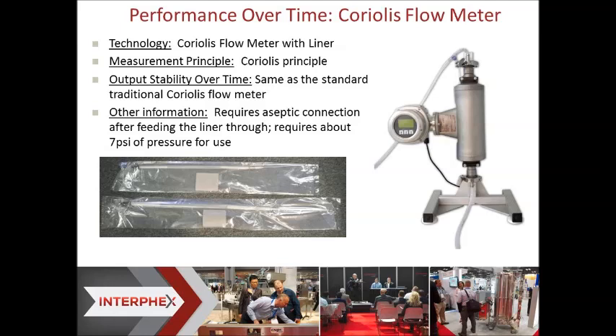As far as the Coriolis flow liner, this technology allows you to use a traditional Coriolis flow meter and eliminate the need for any cleaning or cleaning validation and potential sterilization. It does require an aseptic connection because it needs to be fed through the liner, and it requires about 7 psi of pressure for use. So there's a lot of people that want to use this technology, but they maybe don't have pressure in their process. But it's technology that could be used for a very lengthy period of time.